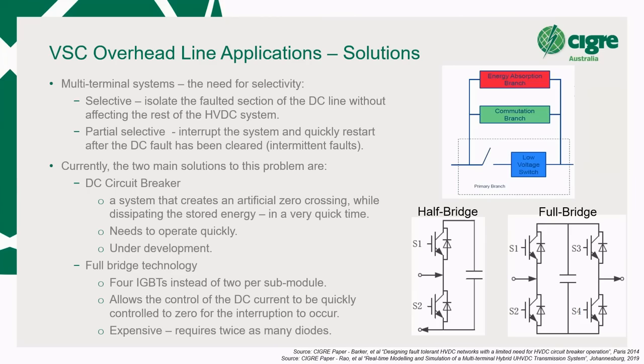The DC breaker, the technology, the innovations that are happening right now, are trying to create an artificial zero crossing. And the most common that you'll see talked about is the hybrid DC circuit breaker, which is where I've got a diagram of it up here. Basically, you've got a high-speed DC switch, and it's in series with this small low-voltage switch. I will make a point. You could make a DC circuit breaker by building a whole lot of IGBTs in series and switching them all out at the same time. That would be very lossy. So it's a technical solution, but I think most parties are not really looking at that. They're looking at a way to make a low-loss DC circuit breaker.